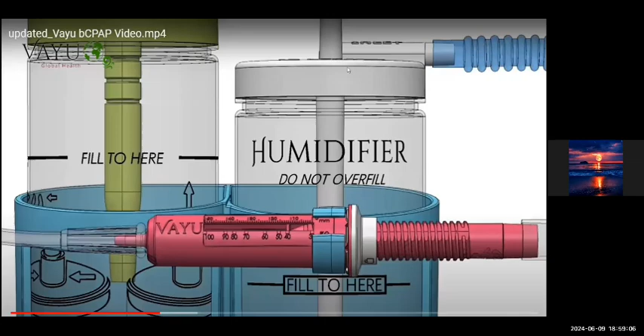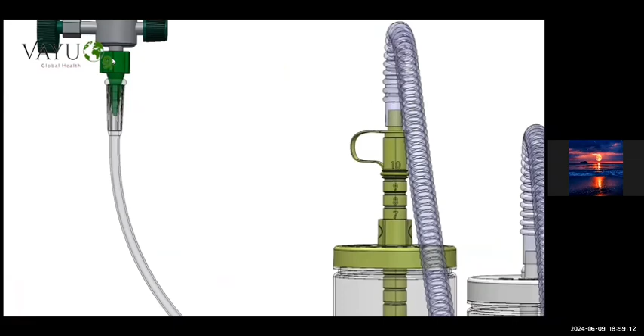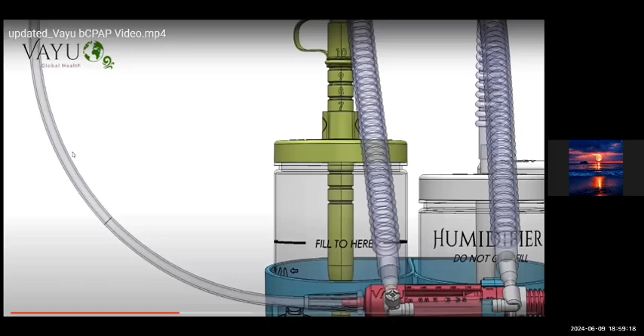Now that the gases are blended, filtered, and humidified, they are ready for the patient to breathe through a pair of silicone binasal prongs. The gases then flow into the pressure generator, which generates pressure to keep the baby's lungs open. This can provide from 4 to 10 centimeters of water pressure, depending on the depth of the wand.